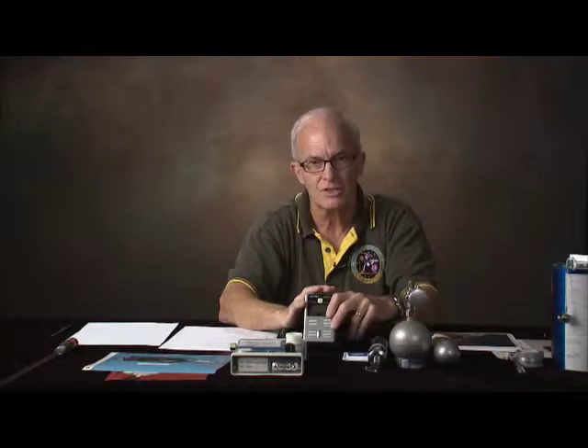One other issue with this analyzer was whether it ought to alarm, where it ought to alarm, and how. There's a caution and warning system in the space station, and we asked: is this thing loud enough to be heard? Do we need to plumb it into caution and warning? One thing we've learned is if you're going to plumb something into a distributed system like caution and warning, you're going to pay a real price in dollars and anguish getting it into that system. So if you can make a standalone analyzer, it's a good thing.